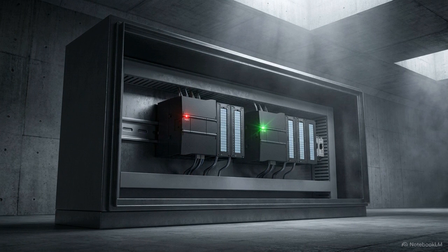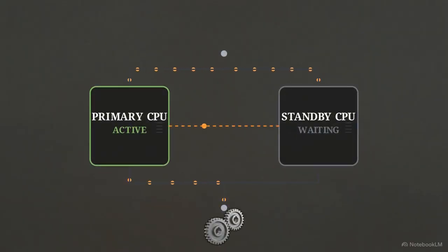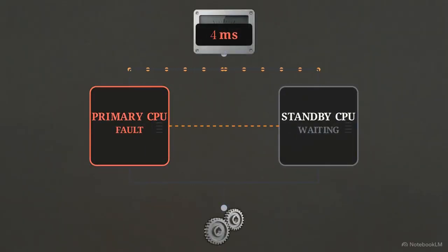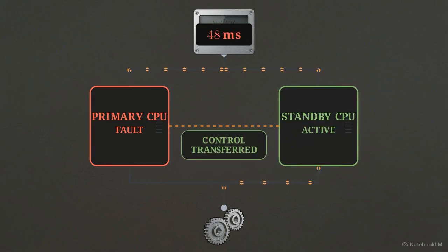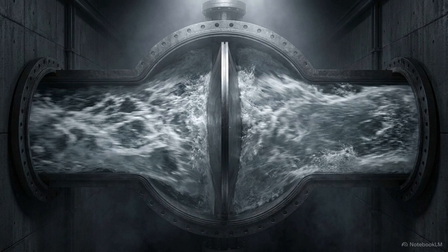Simultaneously, the automation layer responds. On uninterruptible UPS power, the dual CPU PLC executes a bumpless transfer. If the primary processor faults due to the power anomaly, the backup CPU assumes total control of the plant logic in less than 50 milliseconds. Transitioning processors in under 50 milliseconds ensures the digital memory holding the valve positions doesn't wipe, preventing the motorized valves from defaulting to a closed position while water is still moving.